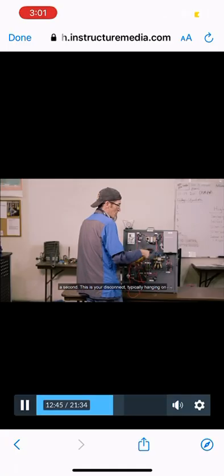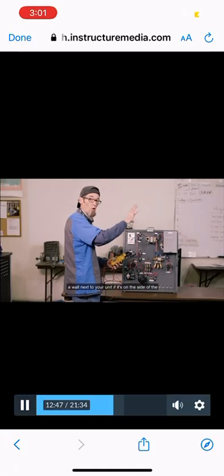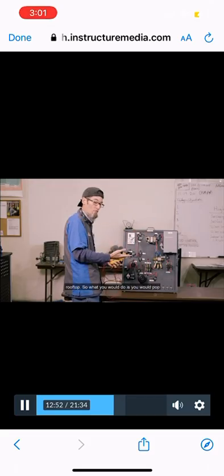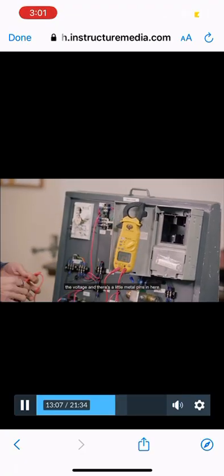So I'm going to move my meter here for a second. This is your disconnect, typically hanging on a wall next to your unit if it's on the side of the house, or it'll be hanging on the unit up on the rooftop. So what you would do is pop this thing open, and typically I would pull this screw off down at the bottom, and I'd be looking for some voltage. But what I'm going to do is pull my fuse box out here. I'm going to take my meter and put it up here so hopefully we can see the voltage.